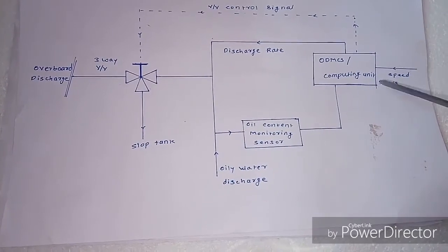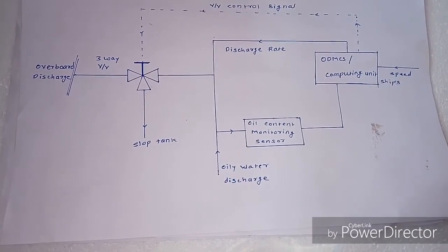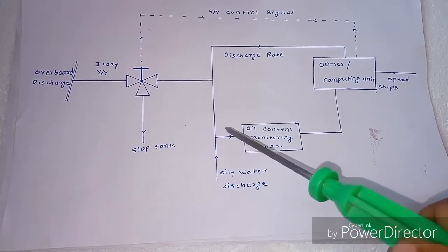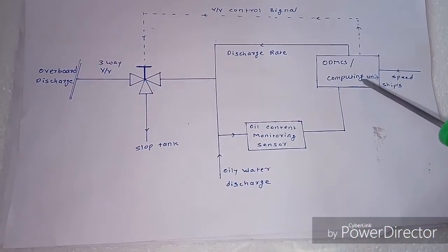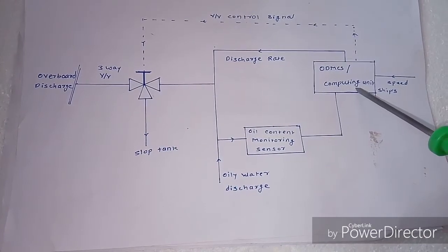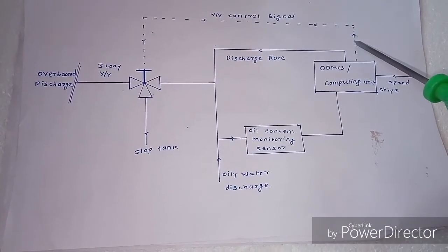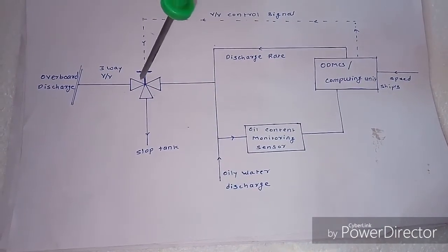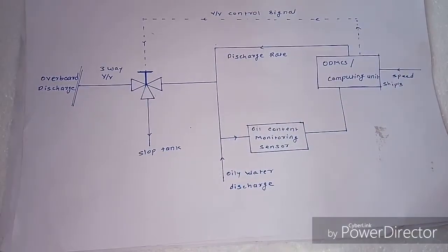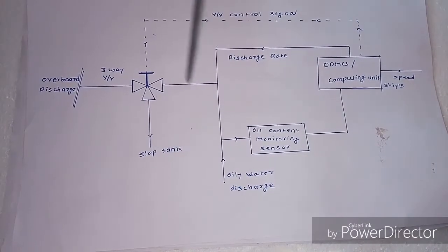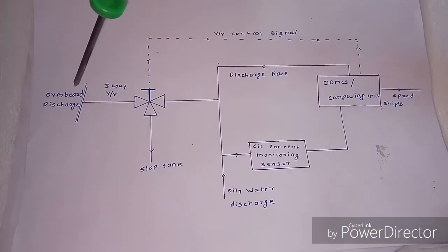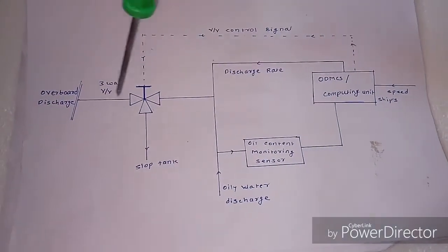Whatever ppm value is transferred to the computing unit, it is calculated and compared with the actual limit — 15 ppm. The discharge water is checked whether it has 15 ppm of oil or not. If it is more than 15 ppm, then the valve control signal is activated: the 3-way valve is closed, the overboard discharge valve is closed, and the flow goes back to the slop tank. If it is not exceeding 15 ppm, then the overboard discharge valve is opened and the discharge is taken overboard.